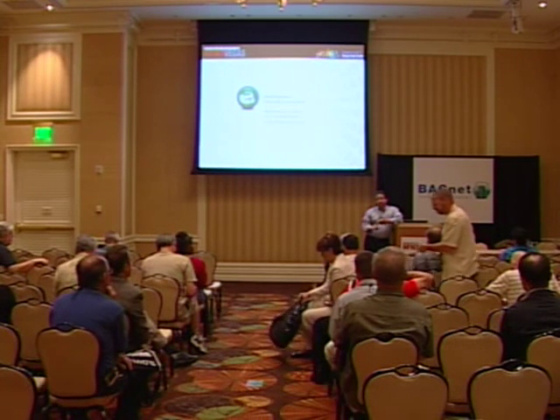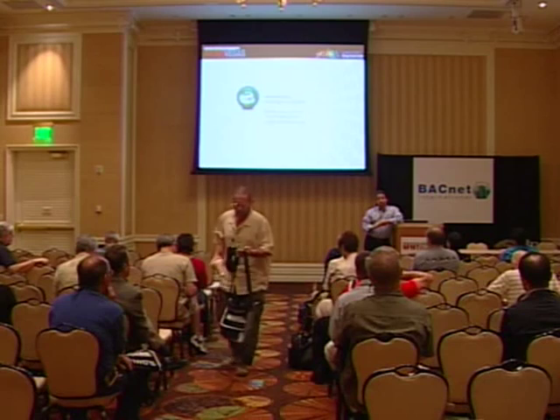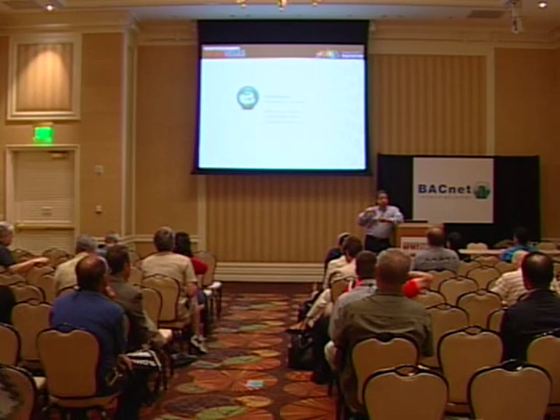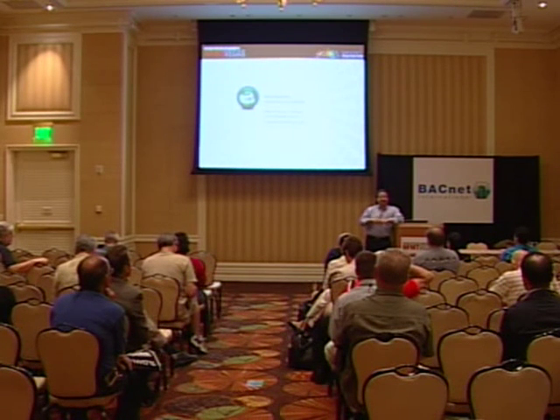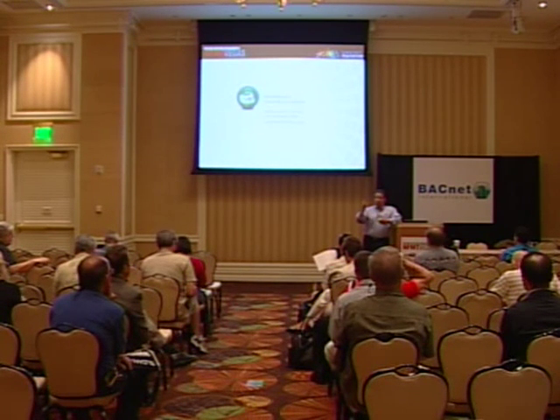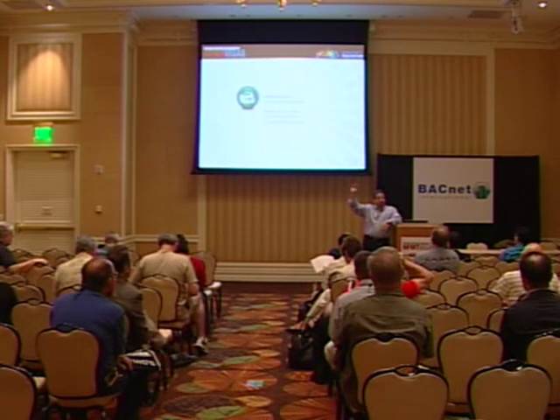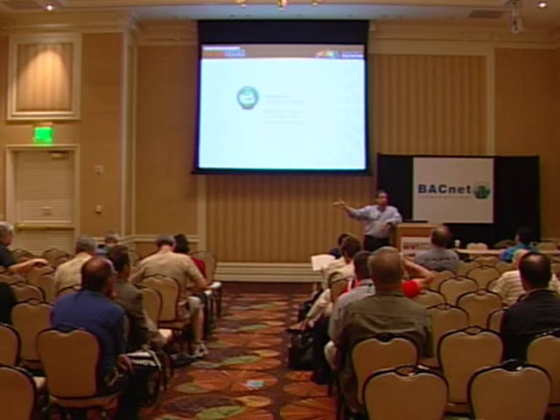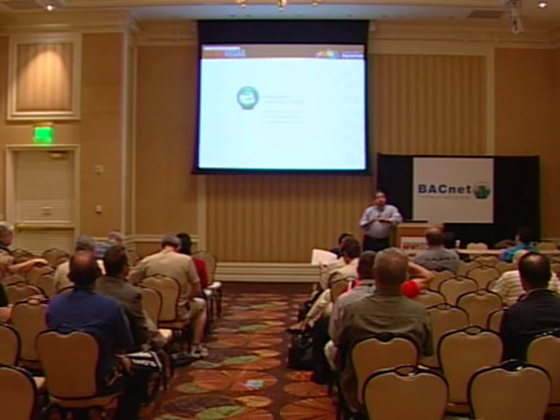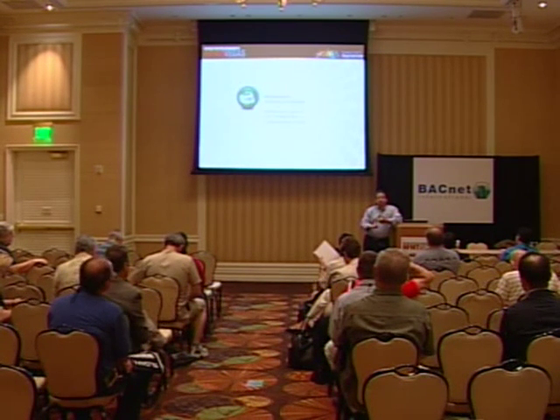As it relates to high bay or exterior lighting, typically there are other manufacturers that make BACnet products other than us — check them out, please, I'm not here to tout what I offer. But what I typically see in, say, an indoor warehouse application is a row of fixtures, fully loaded, typically to 20 or 30 amps. In a lot of those cases, most solutions have been breaker-based control, something like the Square D PowerLink or the Cutler Hammer Power Command style products. Those are the kinds of products we typically see there because the circuit's fully loaded — you're fully utilizing not only the circuit protection function but the control function, and there's a single point of termination for the electrical.